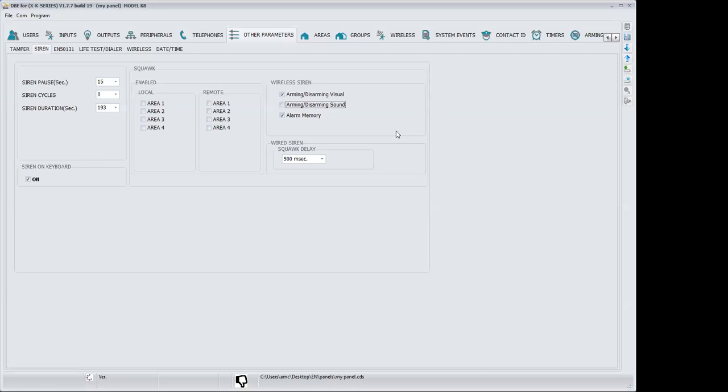The big problem for the life of the battery is not only this type of signal, but the number of alarms per day. From our experience, the battery of the siren works fine. If you use this signal, for example, 2 times per day, for me the life goes over 2-3 years without problem. It's important to understand how many times it goes in alarm. For example, if you have a customer who wants to test the sounder every week, of course the life of the siren is very low, it is short.